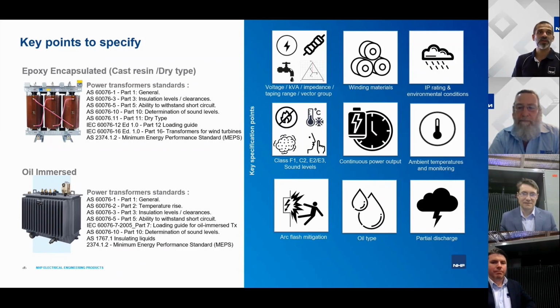Interesting. Thanks, Sean. That's a very, very good point. Moving on, IP ratings. There can be lots of different IP ratings and environmental conditions, as we briefly mentioned before, but also at the same time, it will be covered off in one of the next upcoming webinars, and we'll unpack that a little bit further. With regards to classes, there are different classes around environmental classes, which Dimitri mentioned. Also Dimitri earlier mentioned the climate conditions, which are more referring again to cast resin transformers. There's also a fire classification with regards to the same type of transformers as well. And then one of the other parameters that comes into play is sound levels, because especially for indoor applications, that could be a point of consideration, and it is something that's mentioned in standards again. Power output, obviously the continuous power output of the transformer is what you want to look at.